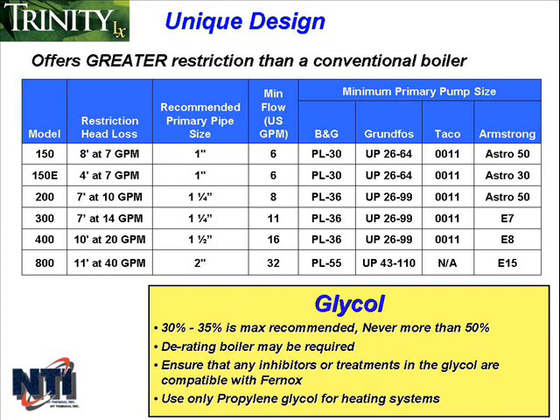There are also a couple of things to keep in mind when using glycol. Ideally, you shouldn't exceed 30 to 35% glycol in the system, and never more than 50%. If you are using a glycol that has the built-in inhibitor, as most of them do, then don't use the inhibitor that we include with the boiler.